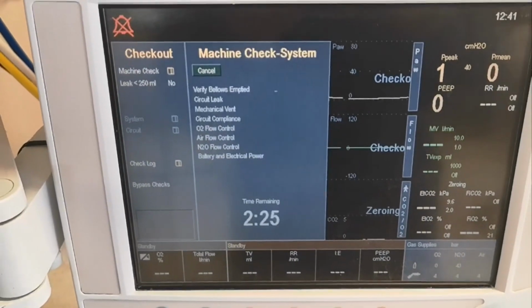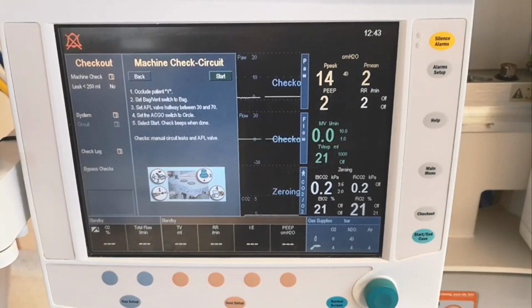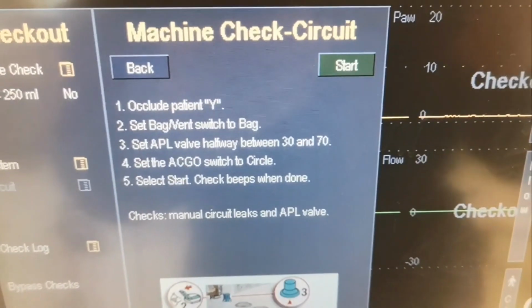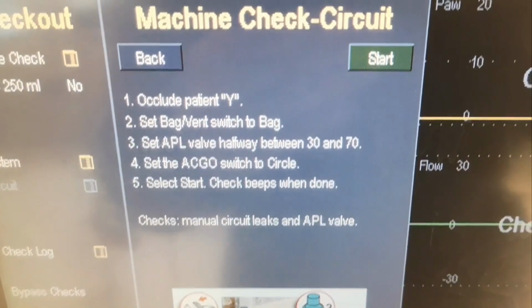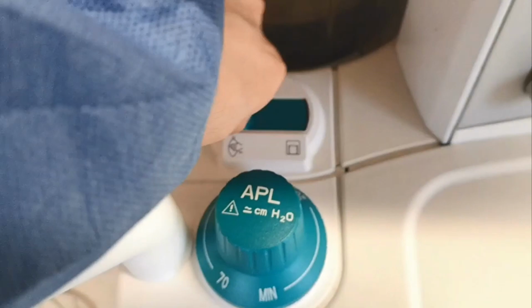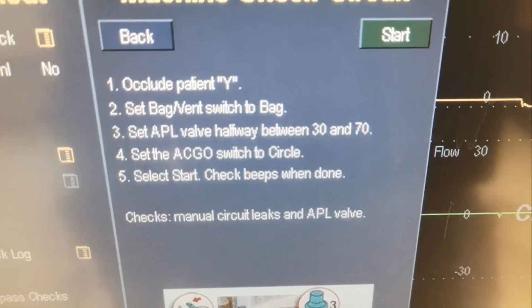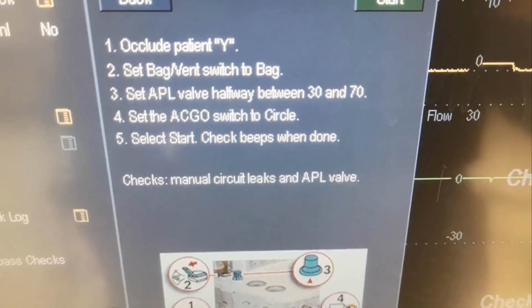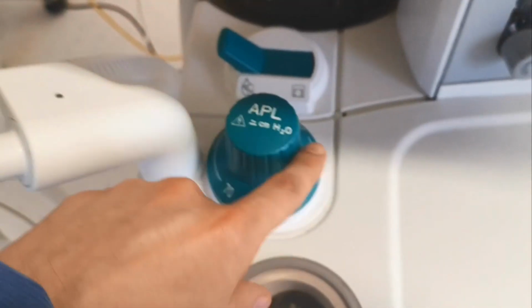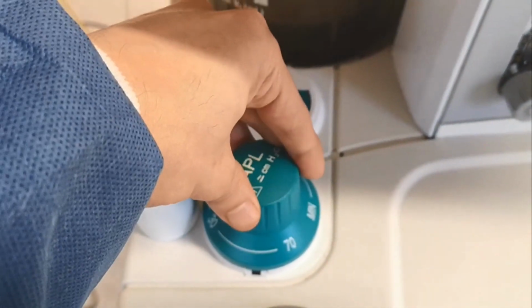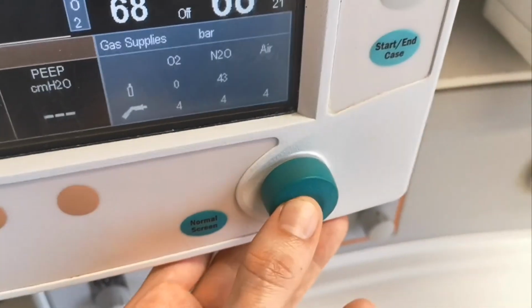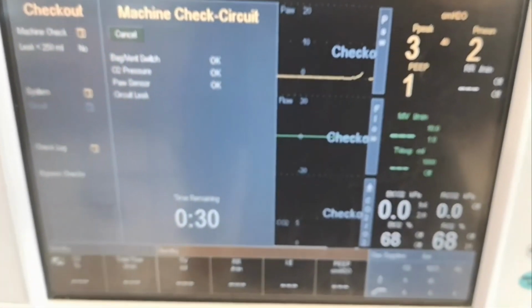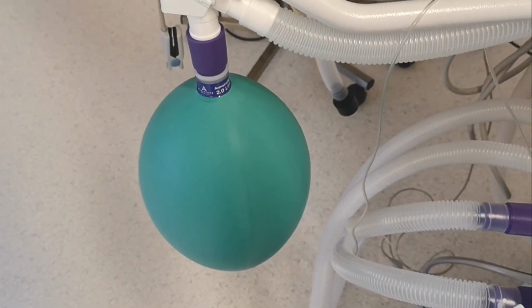You have to wait 2 minutes there, so I'm just gonna pause. Perfect. So now let's see what it says here. Occlude patient Y. Okay, it's already occluded. Set bag vent switch to bag. Okay, that's the bag. Set the APL valve halfway between 30 and 70. Oh, this is the APL valve. Just have to turn it between 30 and 70. And you just click start. Okay. You will see the bag here starts to inflate. This is absolutely fine. It won't explode, don't worry.